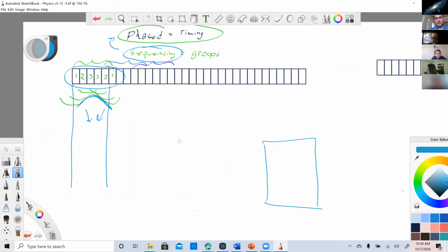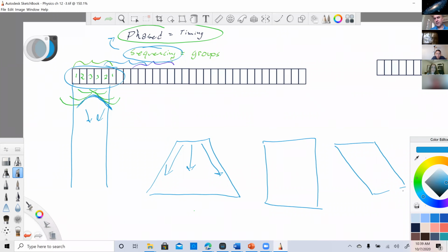We can vector by steering and not steering. So it's kind of like steering in both directions. You create a vector, so that's possible. And of course, we could also take the entire grayscale and steer it. But generally speaking, it is a rectangular image. If we damage this element, we have a shadow. We have dropout underneath that element.